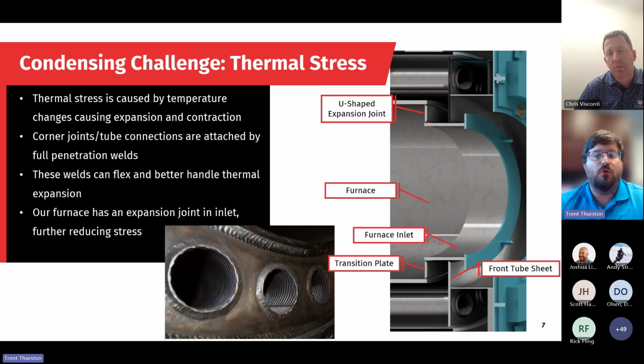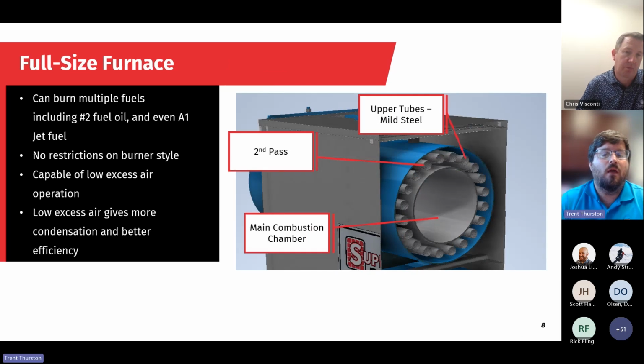As I mentioned, the furnace is going to be the hottest point with, again, over 2,000 degrees. And so this will obviously have the largest thermal expansion because the shell is going to be basically the temperature of the water, which could be as low as 100. So we have this U-shaped expansion joint formed from the furnace, transition plate, and furnace inlet and front tube sheet. This U-shaped joint will allow it to, again, flex even more than just the full penetration welds would by themselves. And so this helps to, again, absorb that thermal expansion. As far as I'm aware, this U-shaped joint is unique to us in the condensing market.